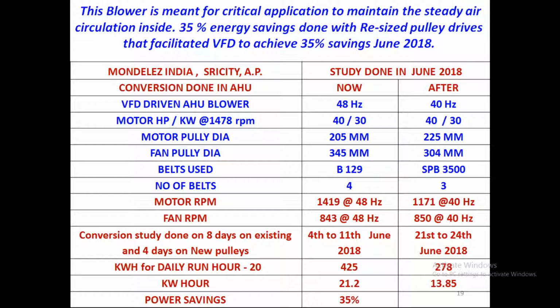You can see it's a 40 HP blower running at 1478 RPM at 50 Hertz. We are able to operate the fan at a lower RPM. You can see on the 5th or 6th line, the fan RPM is operated at 850 RPM. Previously, it was operated at 48 Hertz. Now it is operated at 40 Hertz. The energy savings in kWh were monitored by the company for 8 days, before and after, and we could see almost 35% energy savings is possible on the same existing impeller.